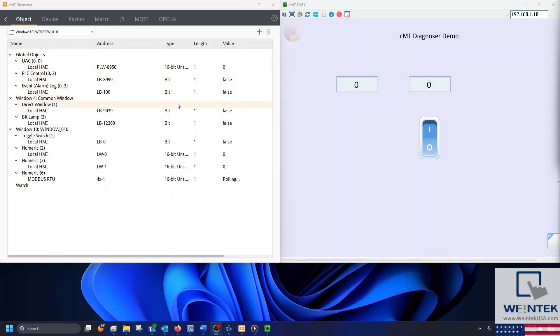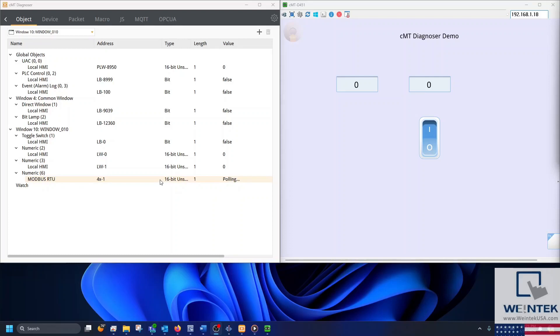And by double-clicking these values, you can write data to them. A value of polling may mean that a device is disconnected, a tag does not exist or that it was changed, or that the HMI is trying to reference a register that doesn't exist or isn't declared within the PLC.